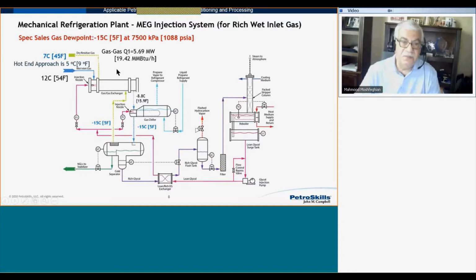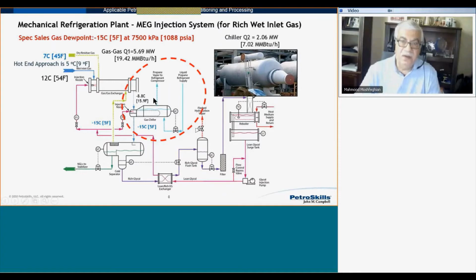So in addition to determining by this process, I can determine the gas-gas exchanger duty, which is listed here for the condition I mentioned, and also determine on the process side the chiller duty, which is the feed to my mechanical refrigeration system. So let's go back and see how we handle the mechanical refrigeration system. But before I go there, the saturated liquid propane goes inside this LCV valve, liquid level control valve, which acts as an expansion valve as well, reducing the pressure. The saturated liquid becomes a two-phase mixture of liquid and gas entering the chiller, and the liquid part vaporizes, removing the heat from process gas.